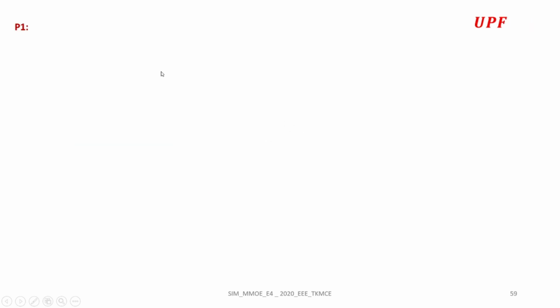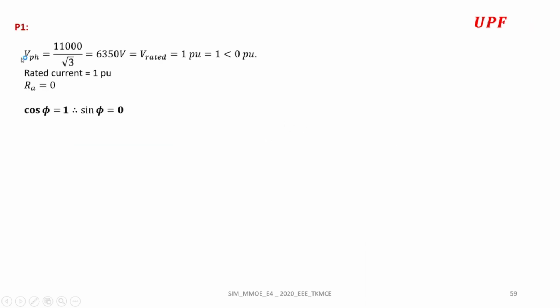Now coming to the unity power factor case, this is the phase voltage, that is 6350 volt. V rated is taken as 1 per unit. Rated current is 1 per unit. Armature resistance is neglected. As the power factor is 1, sin phi is 0. We know the expression for psi under unity power factor as tan inverse of I XQ divided by (V plus I into RA).